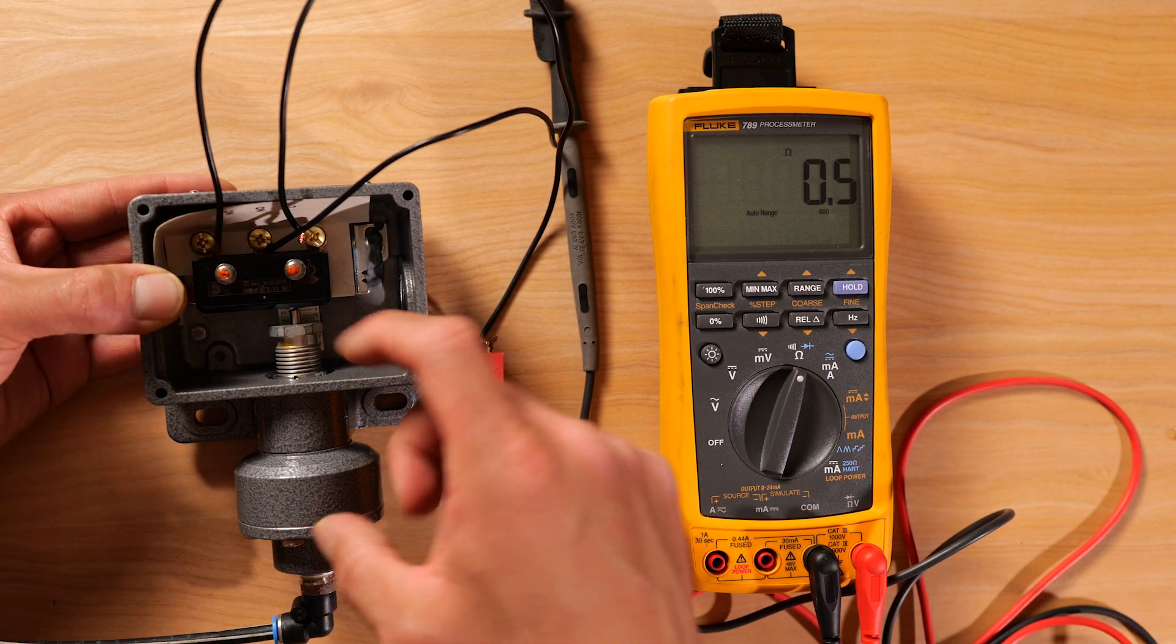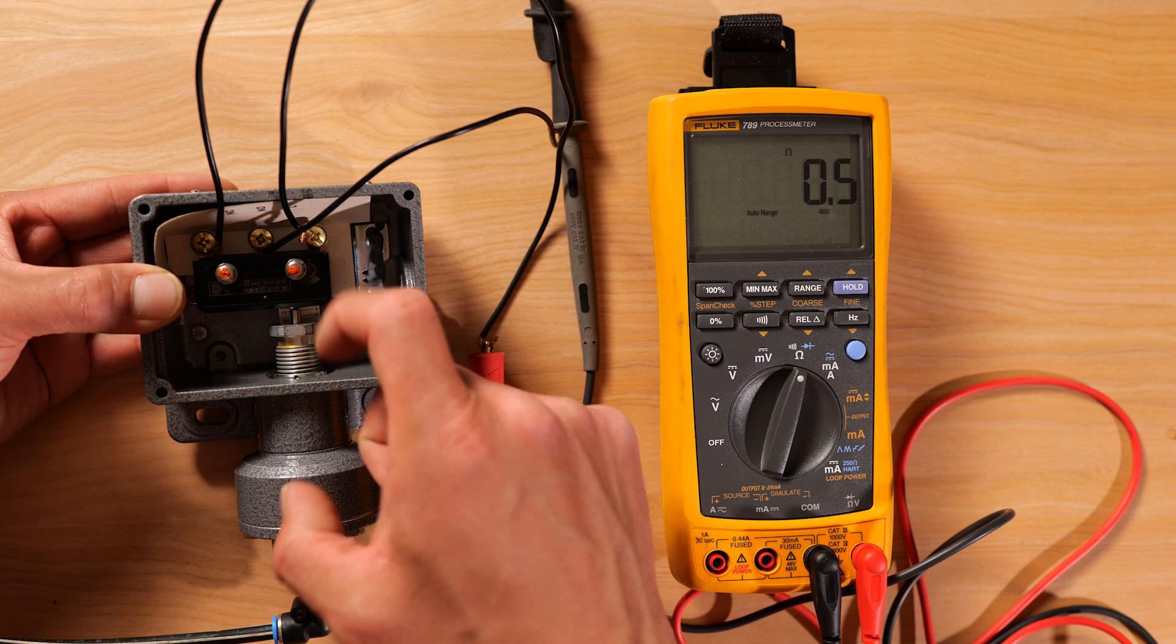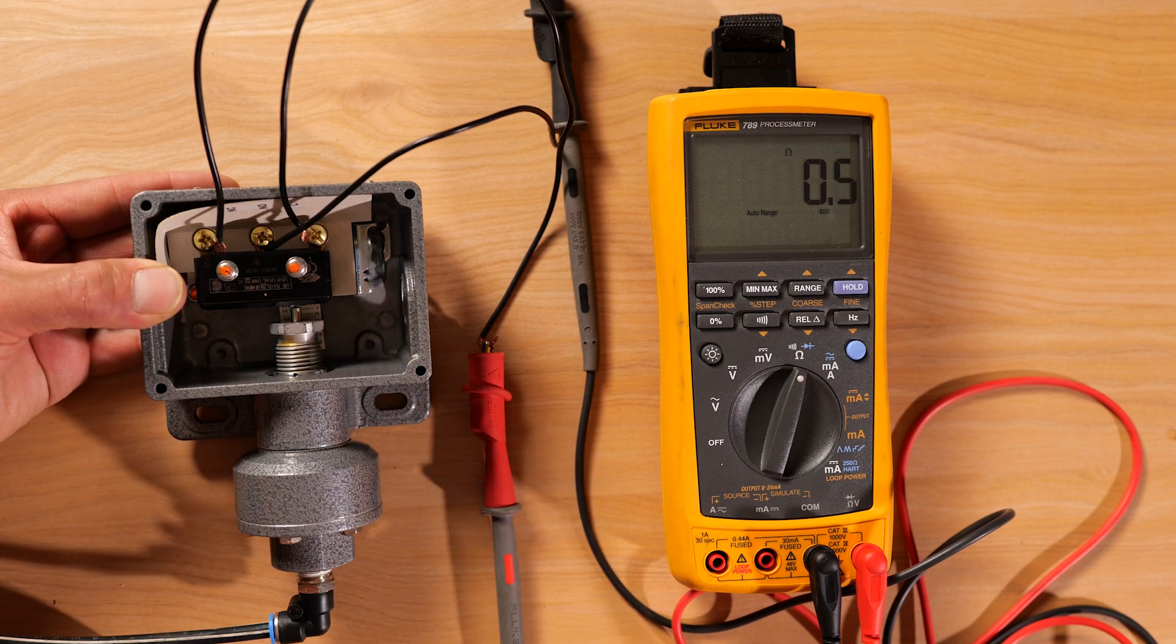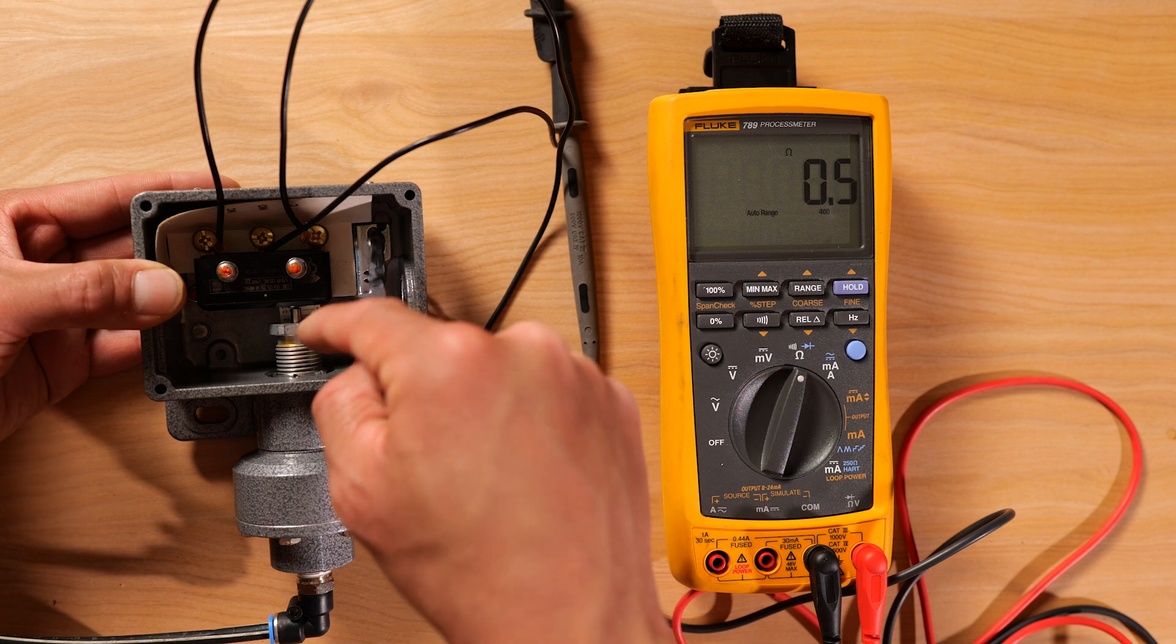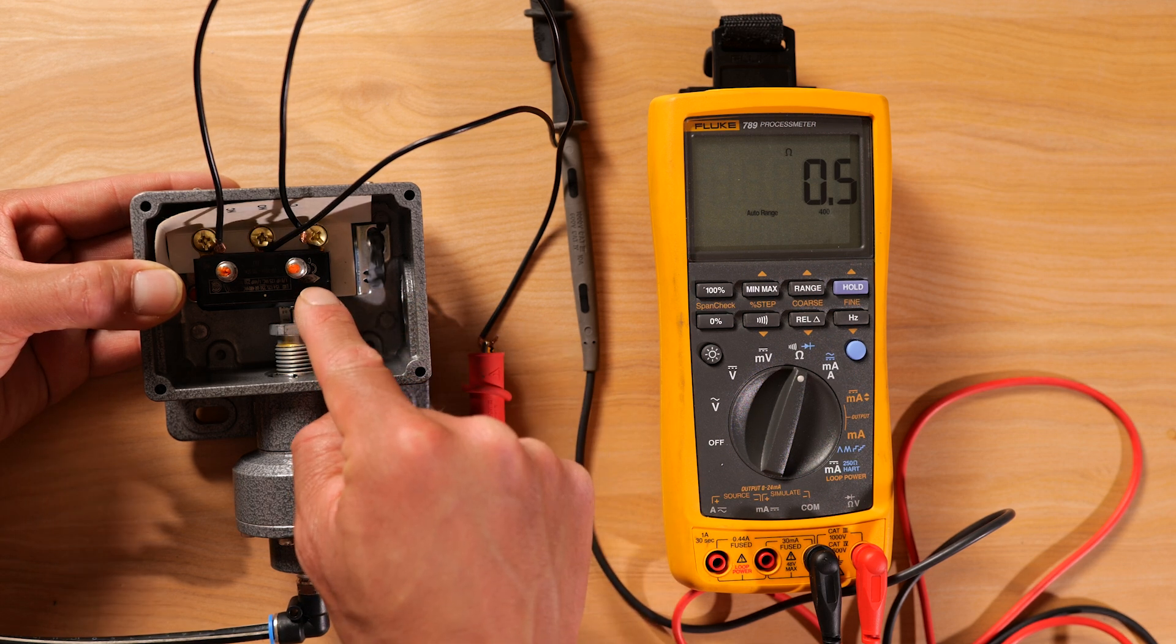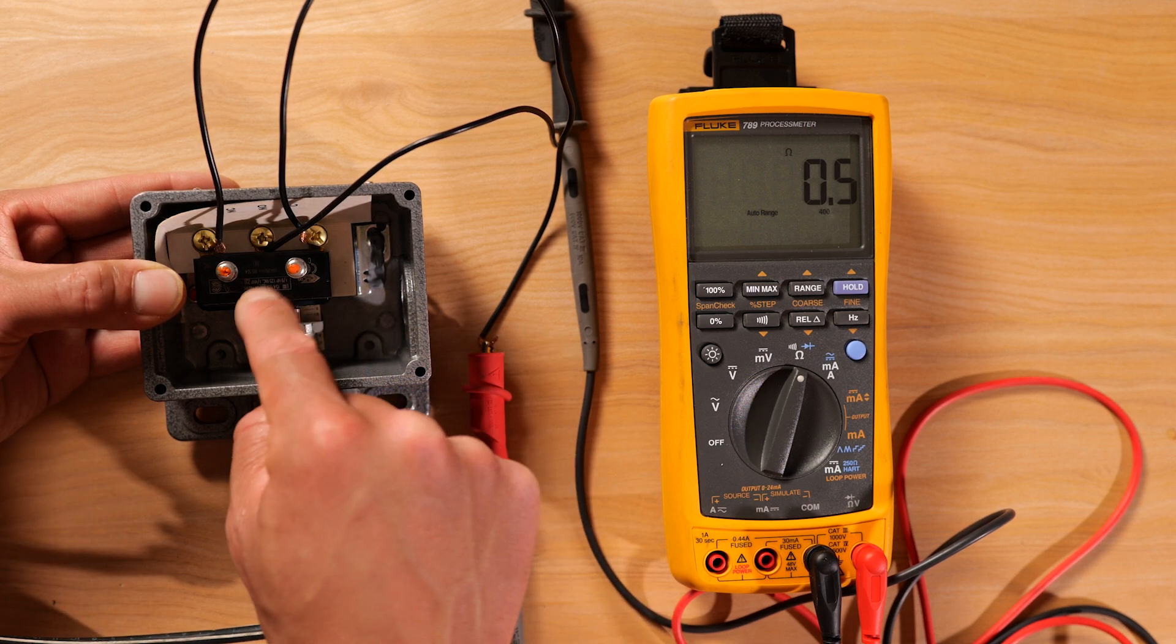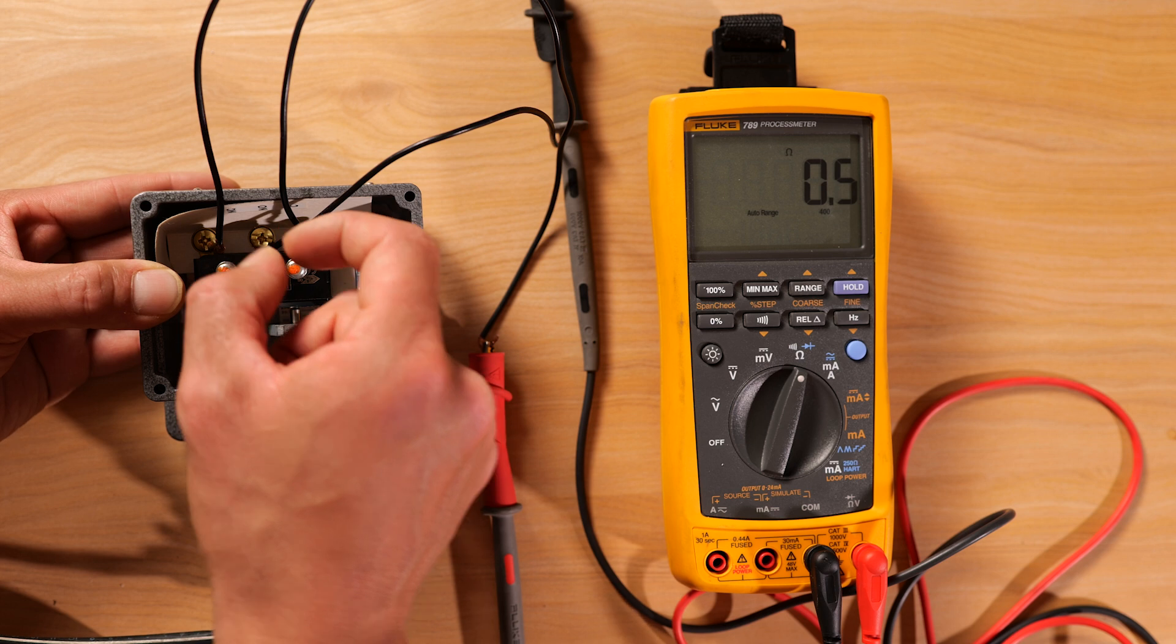And by going down, you're applying more pressure on the spring. By applying more pressure on the spring, now you need more process pressure to overcome that spring to push this nut up. That way it applies pressure on this micro switch, which then changes states.